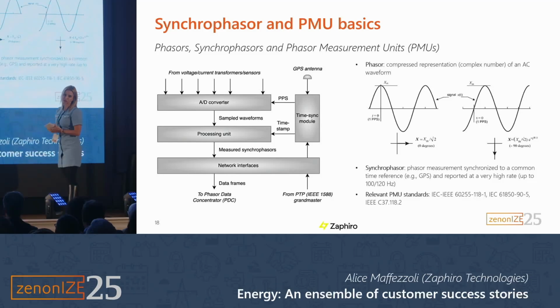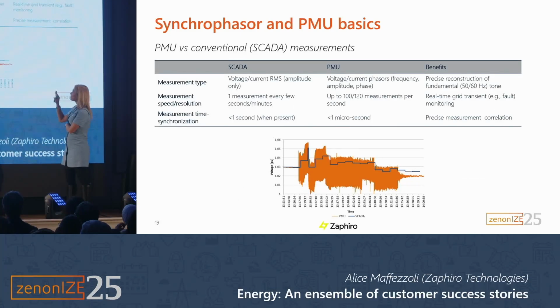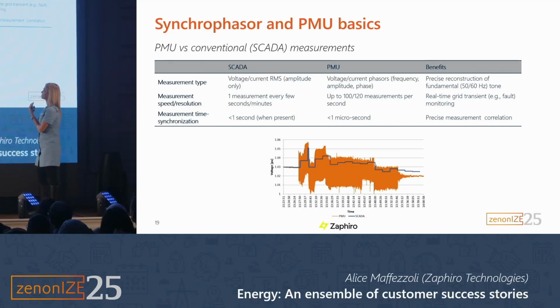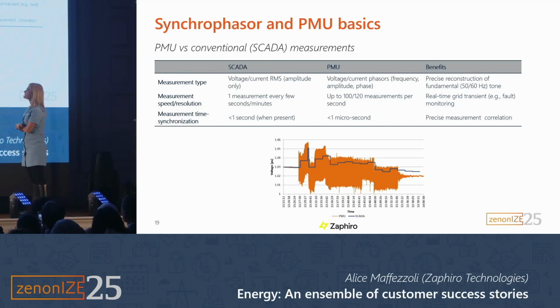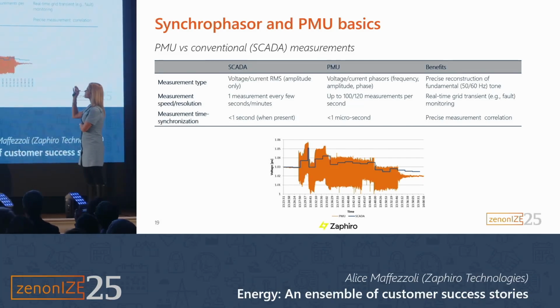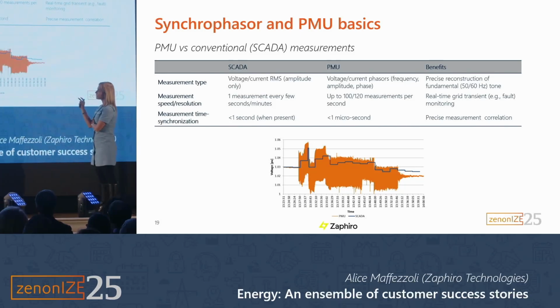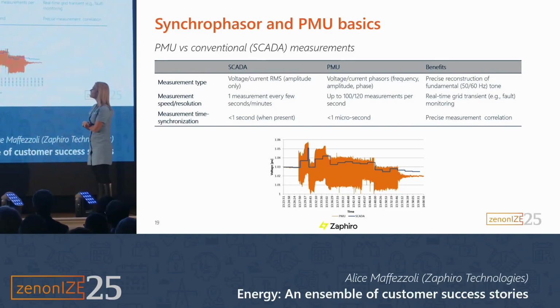So some basics about synchrophasors for those of you who are not familiar with the technology. Synchrophasors are a compressed representation of amplitude, phase angle, and frequency of an AC waveform. When these measurements are synchronized with time, we call them synchrophasors. So just to give you a brief idea of the difference between PMU measurements, so PMUs, Phasor Measurement Units, that measure phasors, versus SCADA measurements. With SCADA, we have measurements of voltages and currents, only amplitude, and the measurements are taken every few seconds or even minutes, with a time synchronization that, when present, has an accuracy of less than 1 second. In the case of PMUs, we measure voltage and current phasors, with measurements taken every 20 milliseconds and with a very precise time synchronization, less than 1 microsecond.